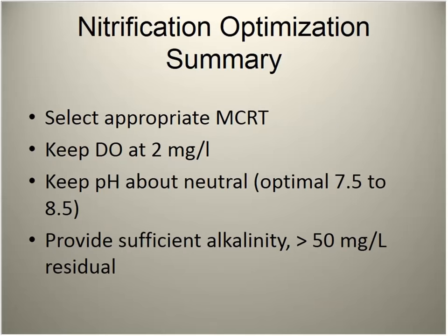Find the right MCRT depending on the temperatures you're dealing with, adjust your wasting rates accordingly, keep dissolved oxygen at a minimum of 2 mg/L, watch your pH, make sure alkalinity is where it should be. A question came in about improving denitrification efficiency — that will be covered in just a few minutes.